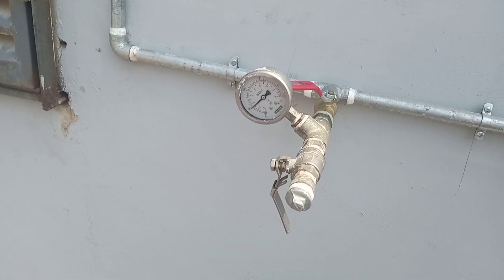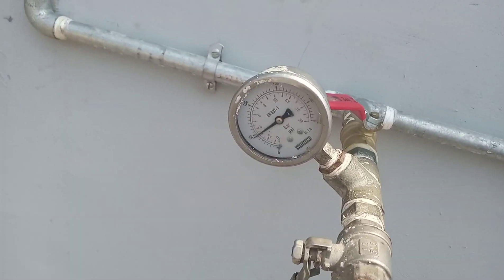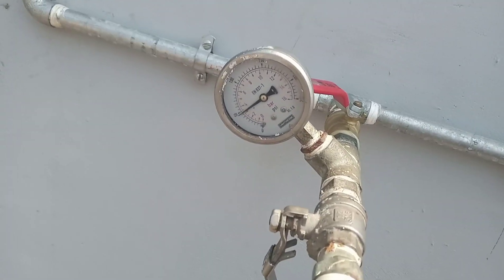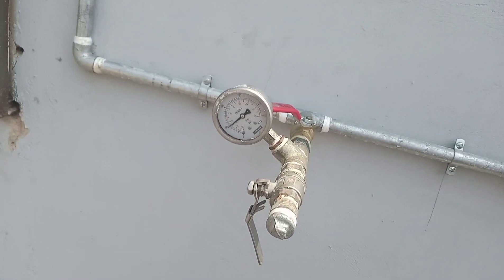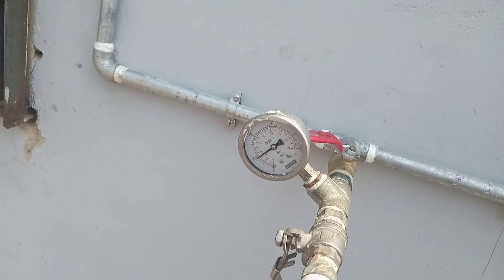We already put the pressure 15 minutes before. Now the drop pressure — the pressure is dropping right now. You can see the PSI is less than 50 right now. We kept it exactly at 50, which is 3.5 bar — we keep this for the long duration.